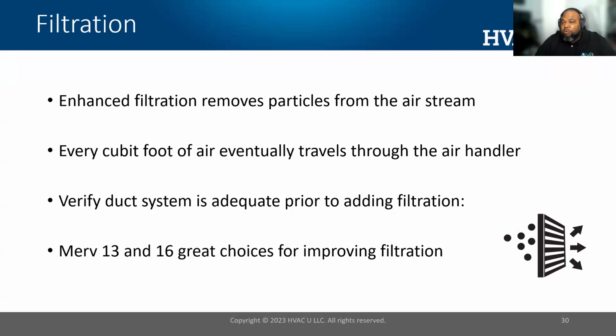So before you implement any kind of filtration system, they do have pressure requirements, pressure drop requirements. So you want to verify that your duct system can adequately handle that filtration system before using that method. Some of the best things that we've seen in our testing, that MERV 13 and MERV 16 are great choices for removing those particles. But again, the pressure drops are significant. It may not be adequate if the duct system isn't modified.